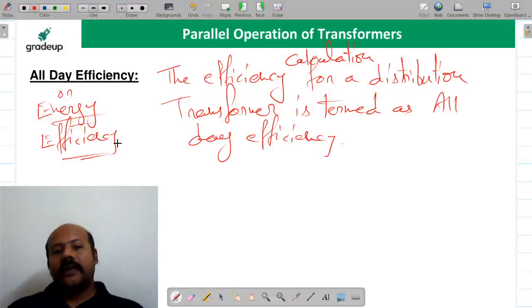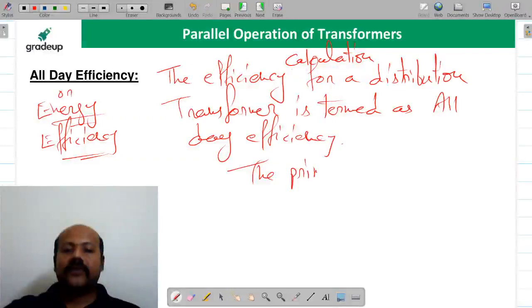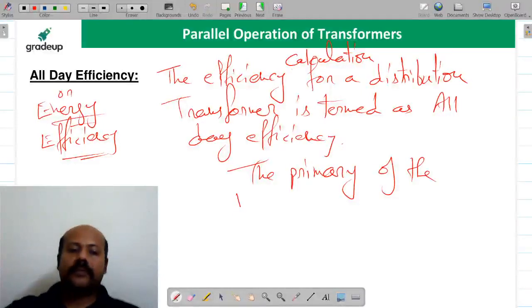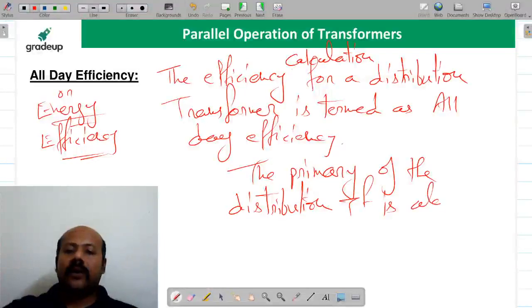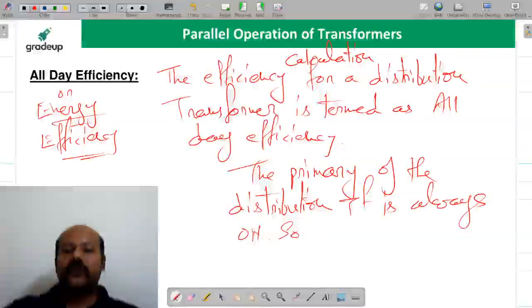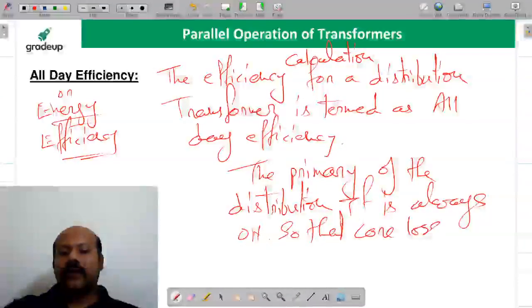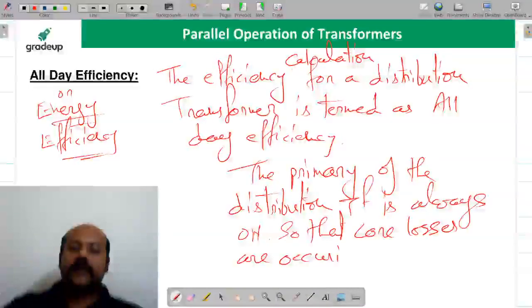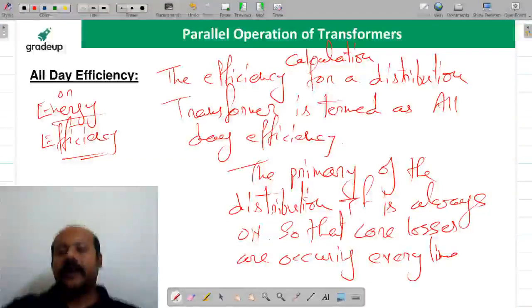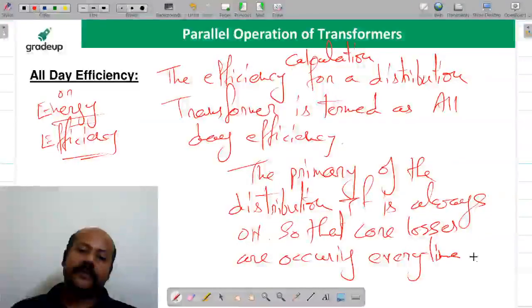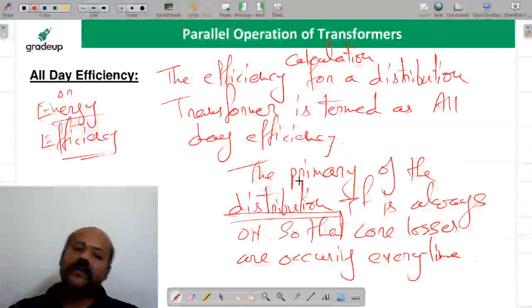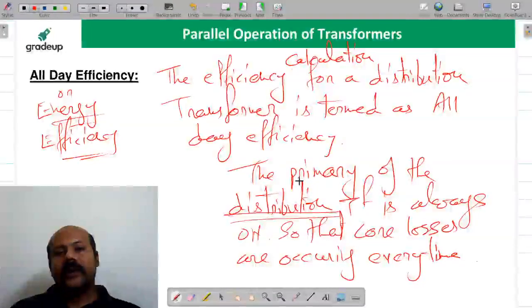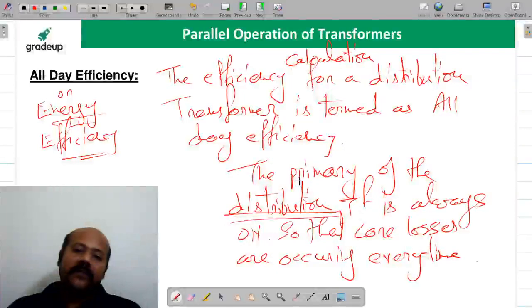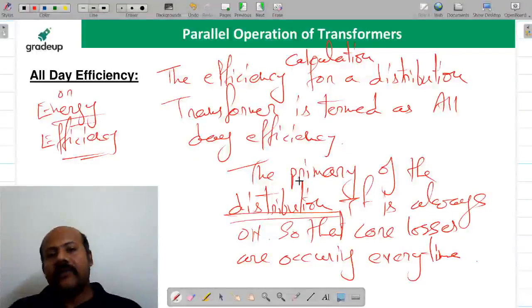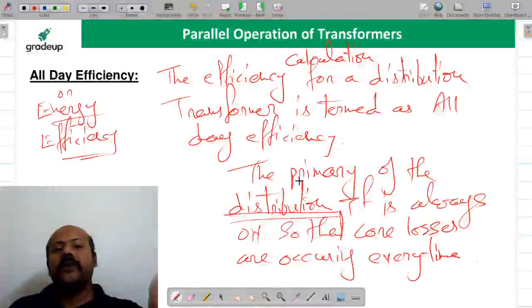What is the reason? The reason is the primary of the distribution transformer is always on, so that core losses are occurring every time. I hope it is clear to all of you. For a distribution transformer, whether there is a load connected on the secondary side or not, the power must be available all the time in the primary side. So definitely core losses are going to occur, whether it is no load condition, full load condition, or any condition in between.